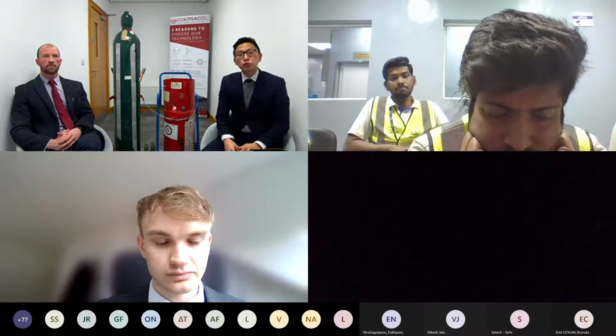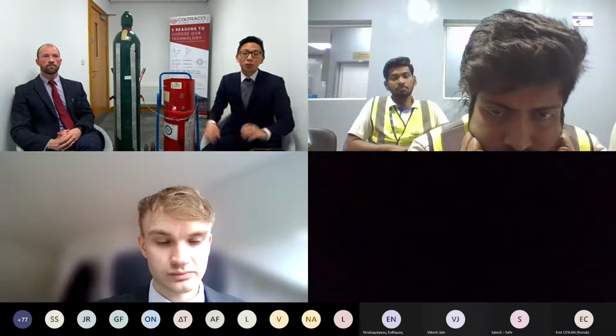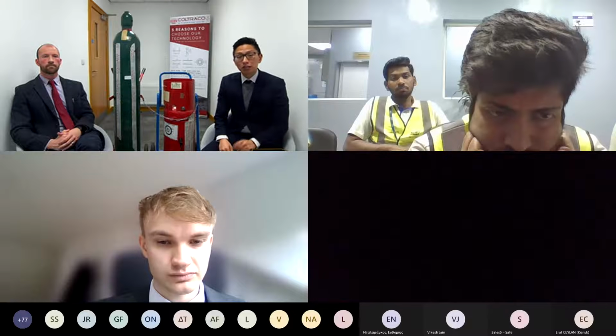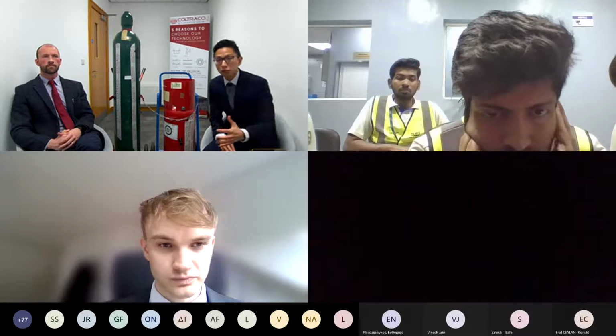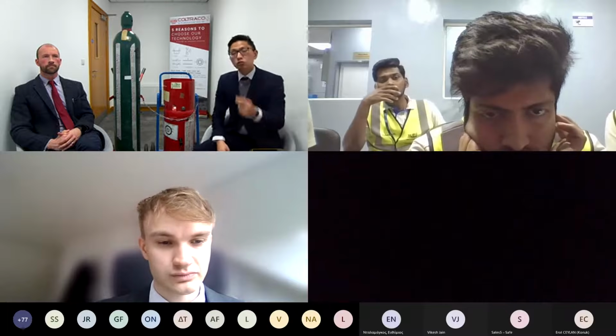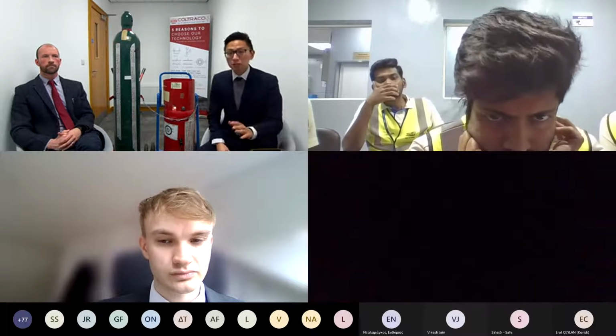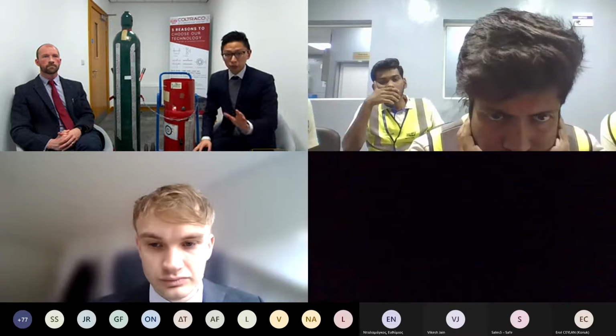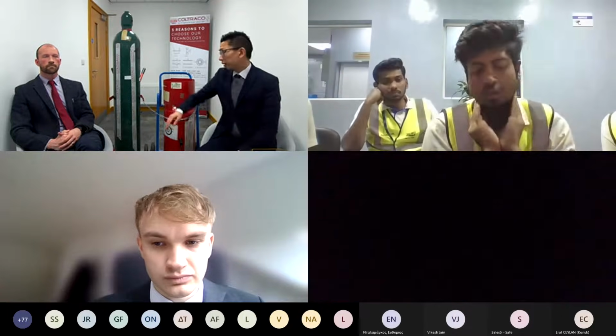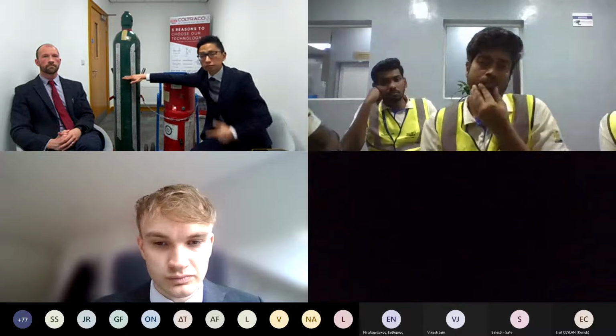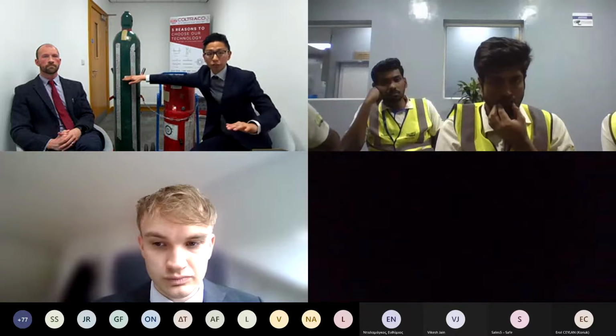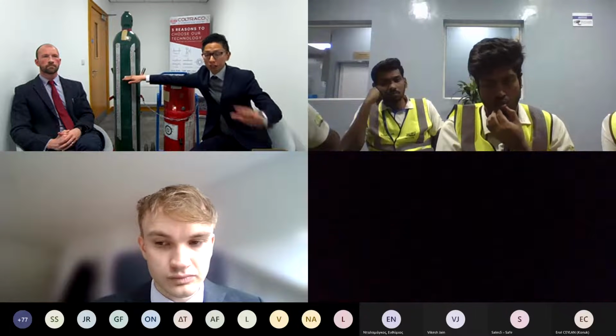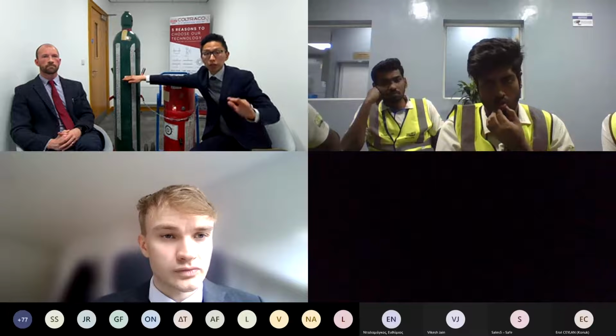So there is no need to maintain temperature at all when you measure CO2 cylinders. As long as it's below 30 degrees, the Portalevel should be able to measure successfully. Now, let me explain why temperature is so important for CO2. For example, if this room is 20 degrees today, you find the liquid level here. If I test tomorrow and the room is warmer, 25 degrees, you find the liquid level here.